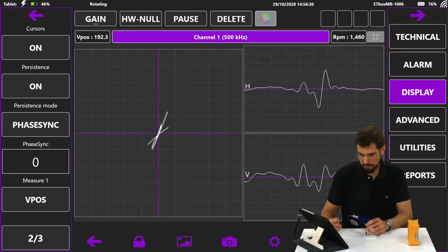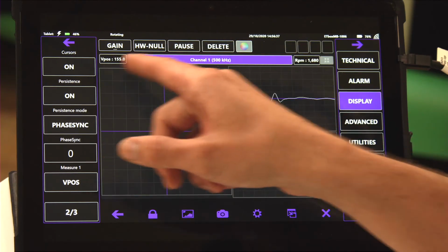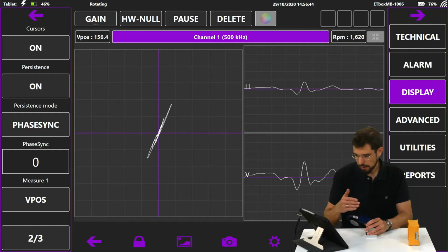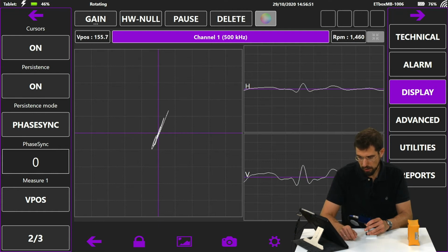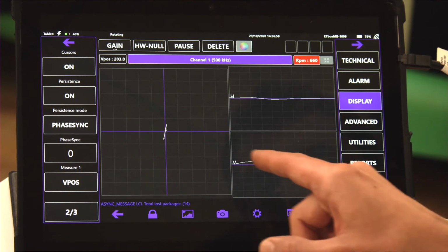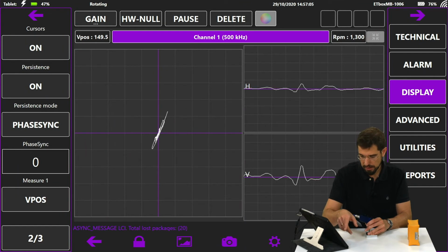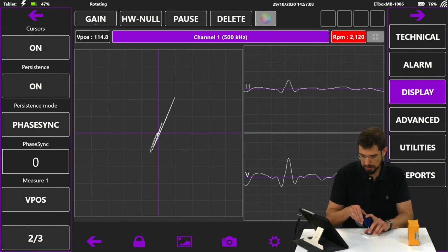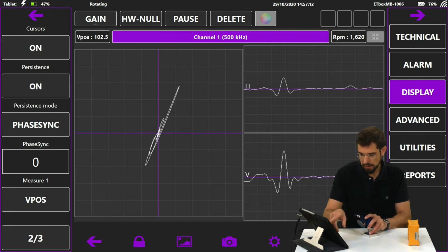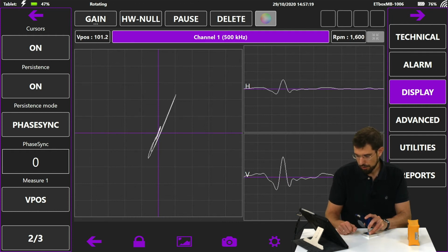Also, within the Display tab, we see that we can configure the measurements that appear in our top toolbar. In this case, there are two differences with the one we had in eddy currents. One of them is that we can put revolutions per minute, and the other is that we can put the VPOS. Here, it's giving us the position that would have the signal of greater entity on the screen relative to 360 degrees. As we have been able to calibrate with phase sync and with a notch, we have been able to tell where the notch was. Here we can measure, and right away, the peak of greater amplitude tells us in what position of the rotation it is.